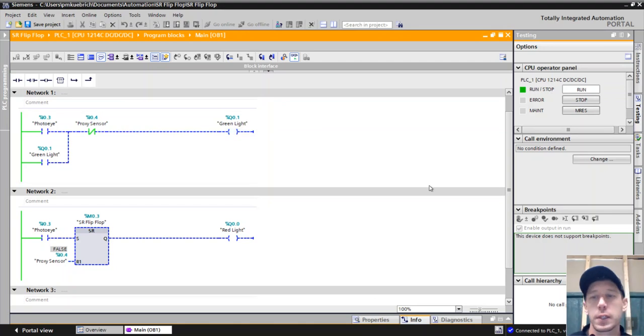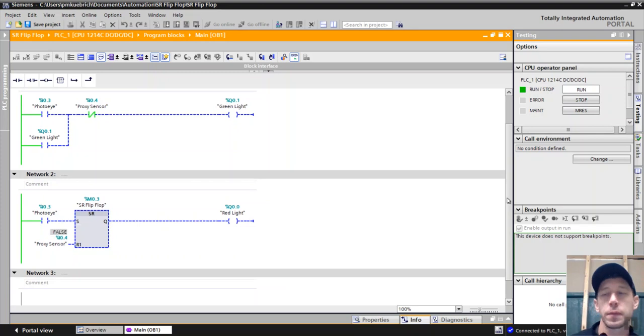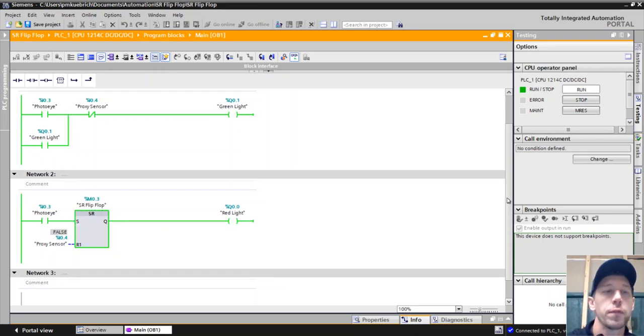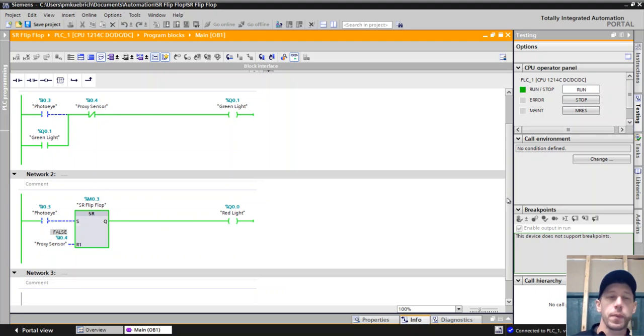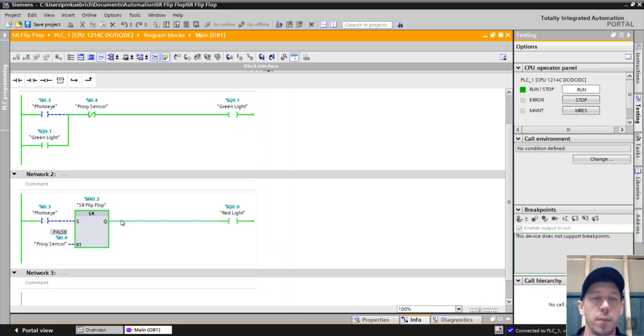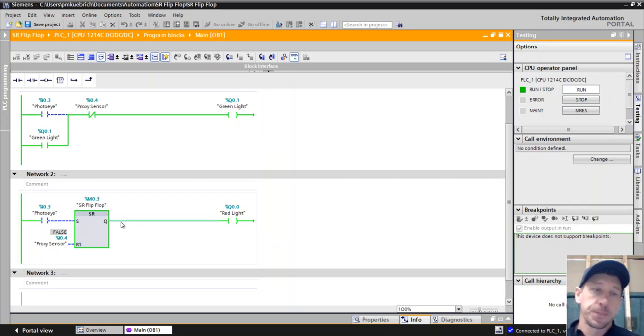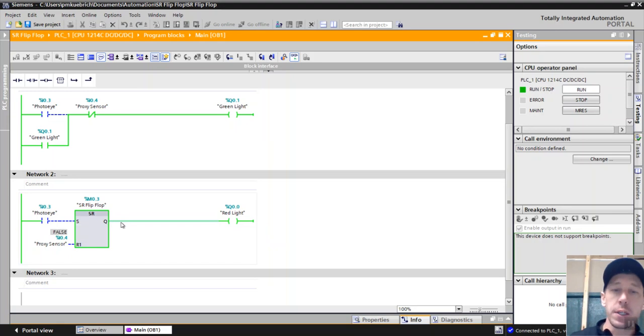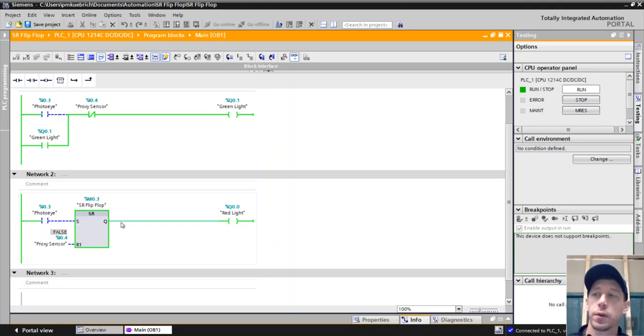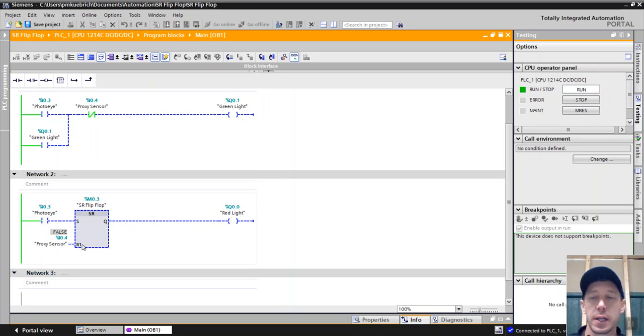If you look down at the next line, you'll notice that this does the same function. We have a photo eye that will set our set-reset flip-flop. That first line will set it. That S means set and that's tied to the photo eye. So that will set this output to true and it will stay true or latch until it gets reset. And that's where the proximity sensor comes in, and that is tied to the input R for our reset.